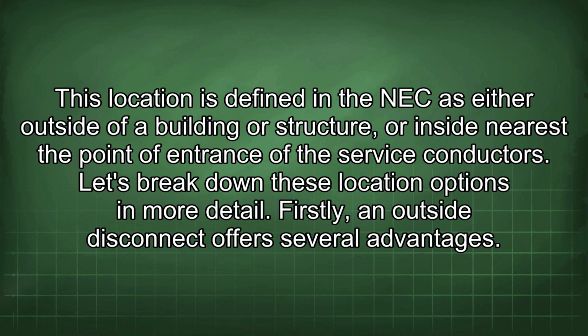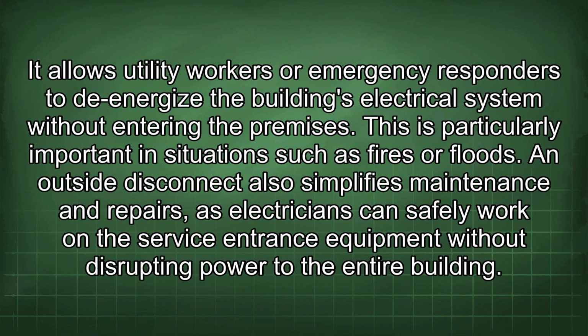Firstly, an outside disconnect offers several advantages. It allows utility workers or emergency responders to de-energize the building's electrical system without entering the premises. This is particularly important in situations such as fires or floods. An outside disconnect also simplifies maintenance and repairs, as electricians can safely work on the service entrance equipment without disrupting power to the entire building.